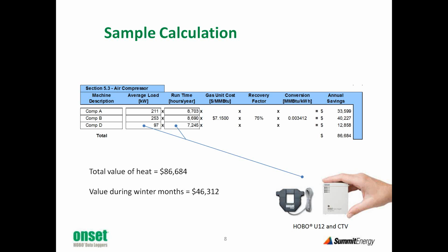Now, we typically would not collect data for an entire year. We would collect it for a representative week or 2 and then estimate the running hours. But from this information and knowing that 75% of the input energy is waste heat, it allows us to calculate the value of that waste heat. In my example, it's $86,684 per year. Now, that's based on a cost for natural gas of $7.15. Your costs may be different, but my point here is that usually it's a significant amount of money.